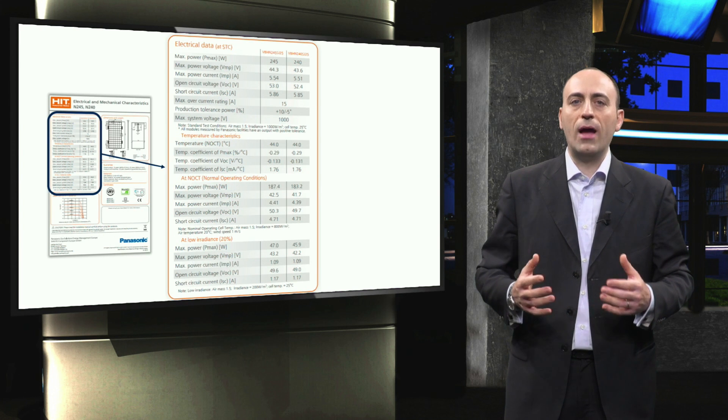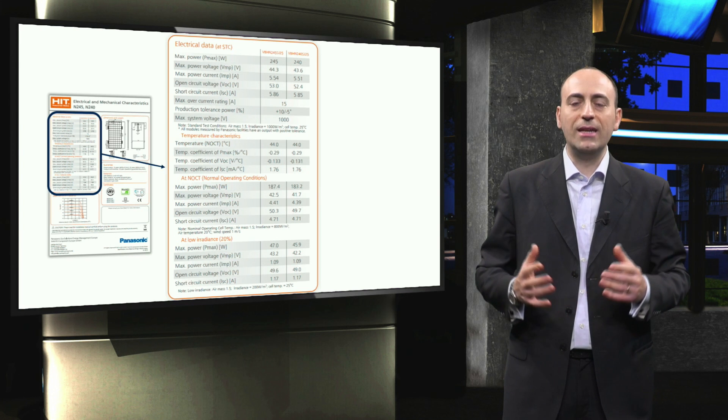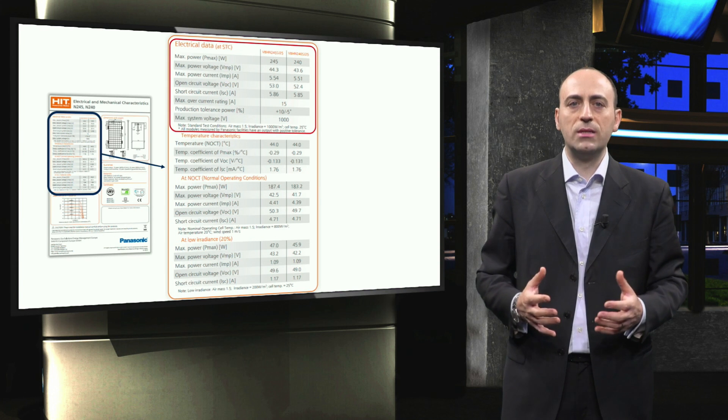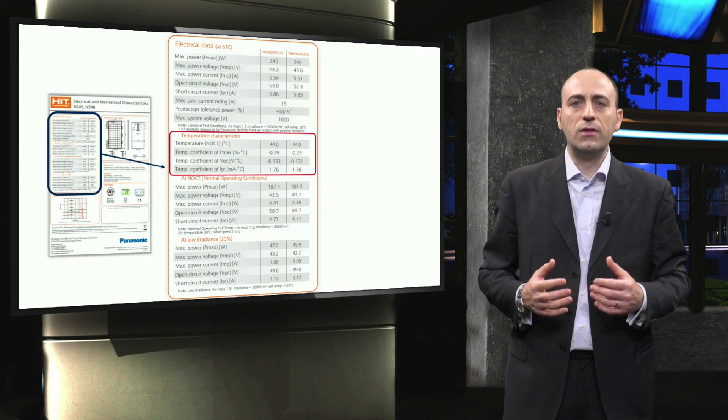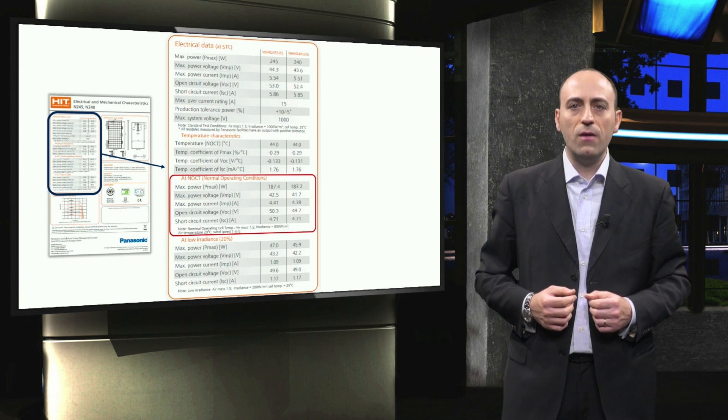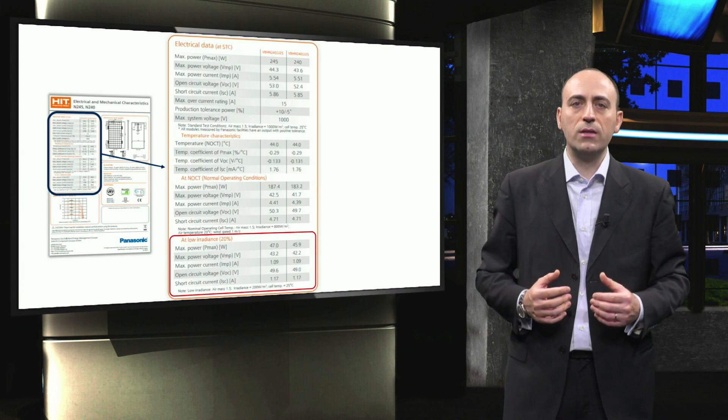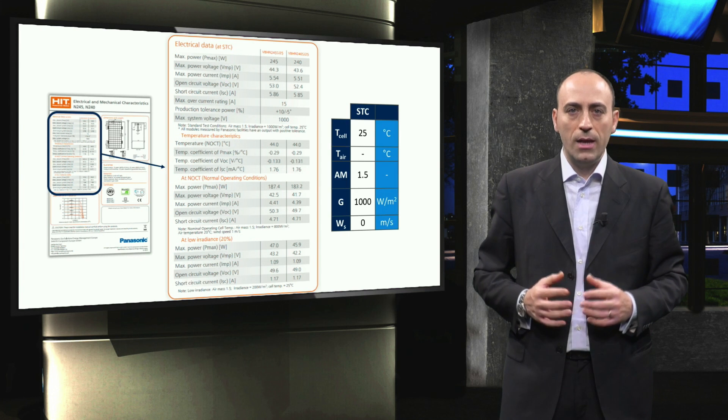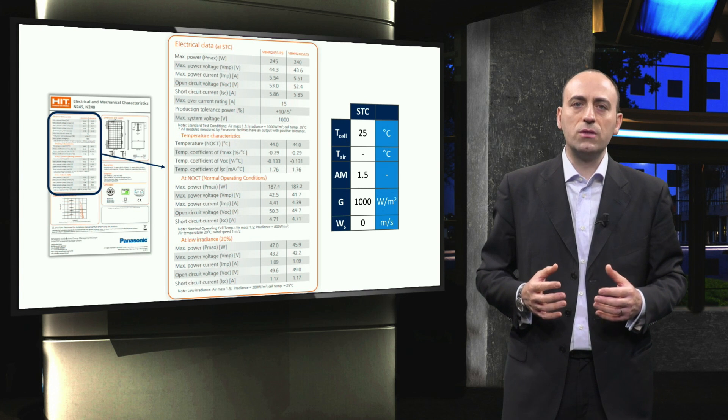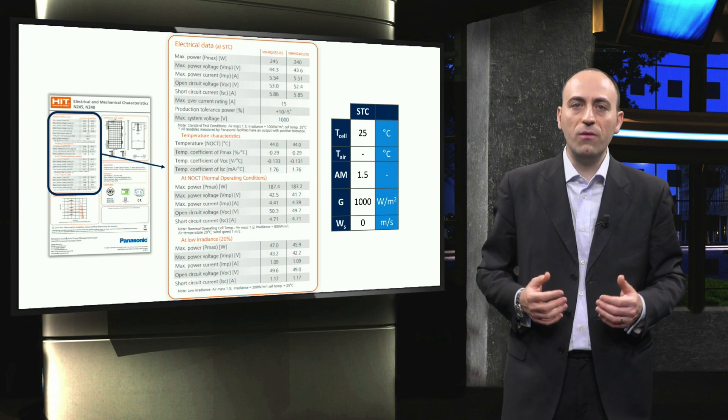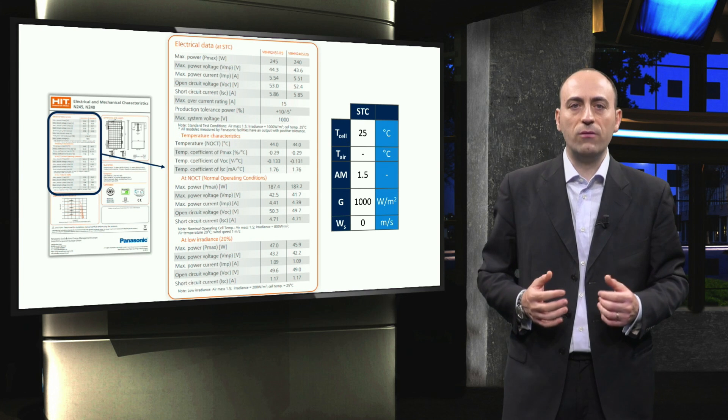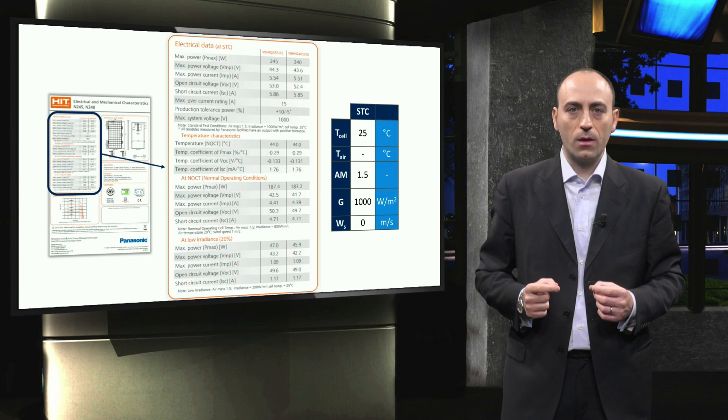Finally, let's take a look at, perhaps, the most important part of the datasheet: the electrical data. These are organized into four groups. The first table provides the properties at standard test conditions. Next, the temperature characteristics are shown, followed by the module properties at normal operating conditions. Finally, the module performance under low irradiance conditions is shown. Let's start with the properties at standard test conditions. As you may recall, the standard test conditions are 1 sun illumination, which is the AM 1.5 spectrum at 1000 Watt per square meter, a constant module temperature of 25 degrees Celsius, and the absence of wind.